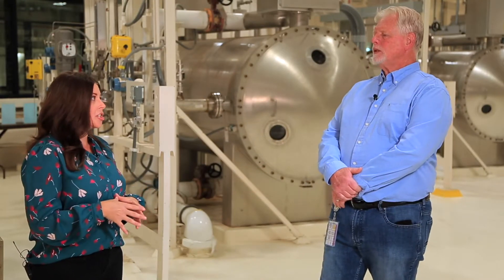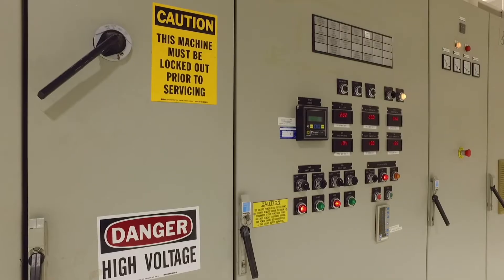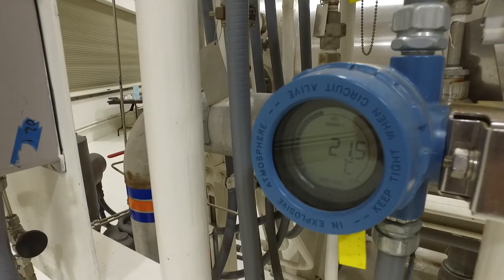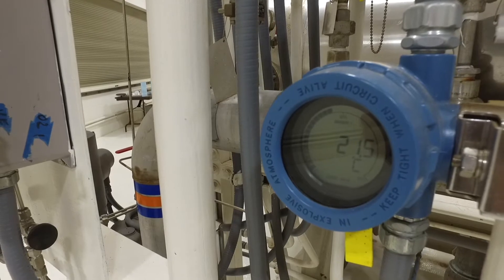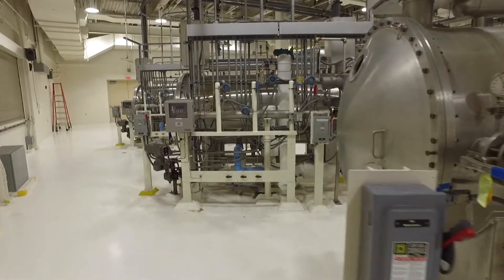We make our own ozonation here, using the machinery and equipment behind us. First, we have to make a gas we can produce ozone with, so the first step is to manufacture oxygen. We run that oxygen through the ozone machine and electrify it. As the O2 molecules are electrified and come apart, many come back as O3. This produces about 10% ozone — so at full capacity, it's roughly 90% oxygen and 10% ozone.